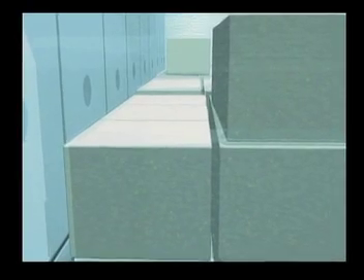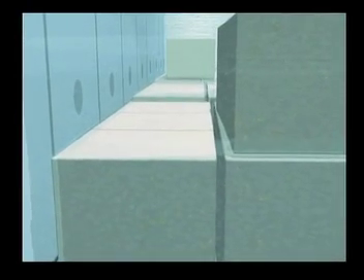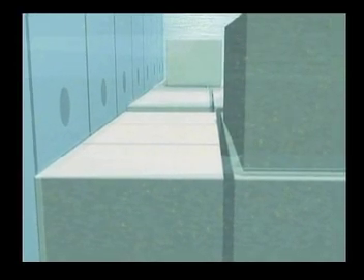This trace amount of gas is not explosive, but it is toxic and must be removed by ventilating the chamber before workers can enter.